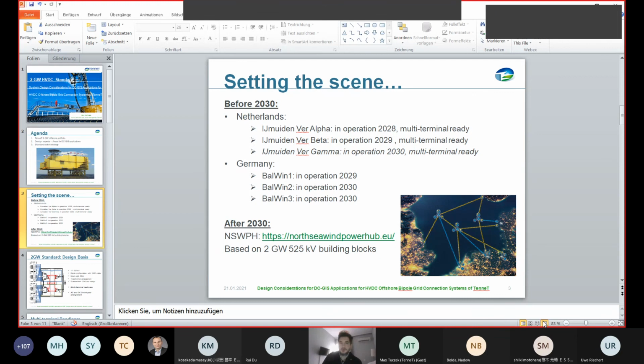A few words about the standard itself: it's based on 525 kV nominal voltage, a bipole application with a metallic return cable, 66 kV on the AC side on the platform side, with a fixed transformer arrangement. We're aiming for a standardized platform design. Important again to say that the system will be multi-terminal ready on the offshore side, meaning the platform itself has the extra space needed for future components.